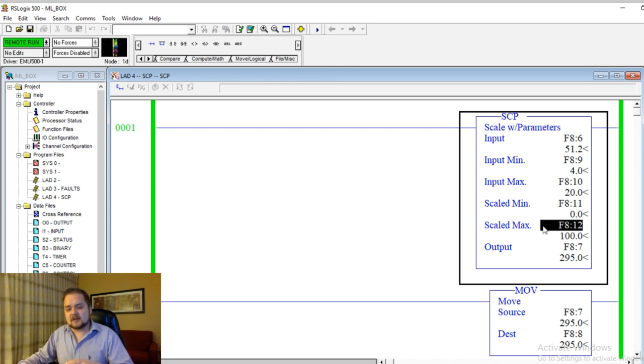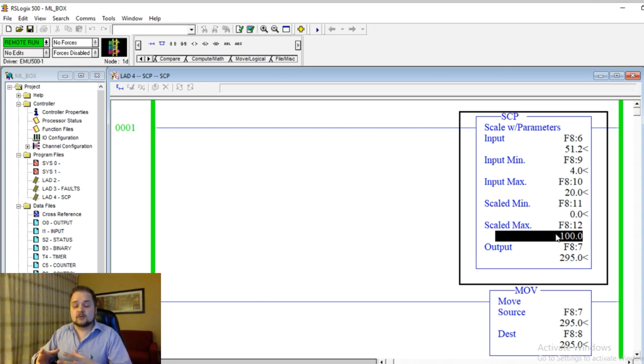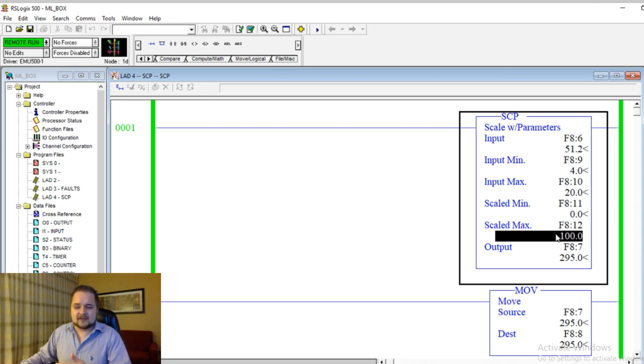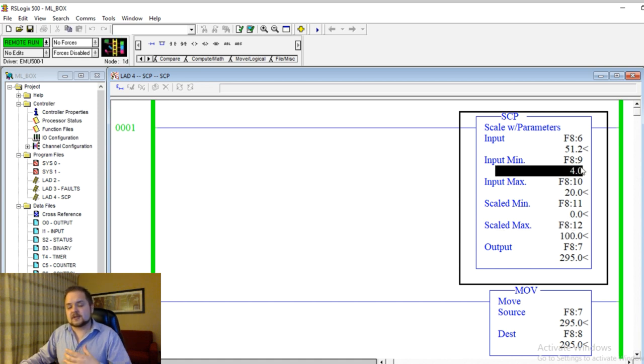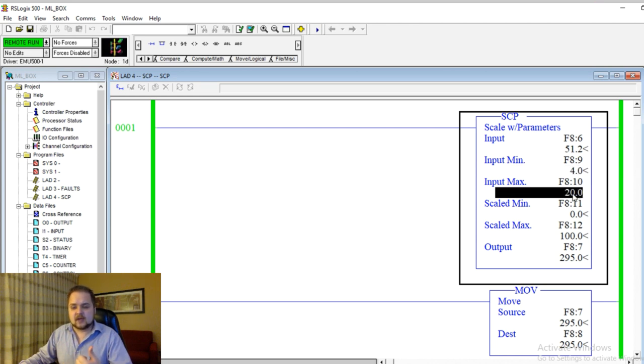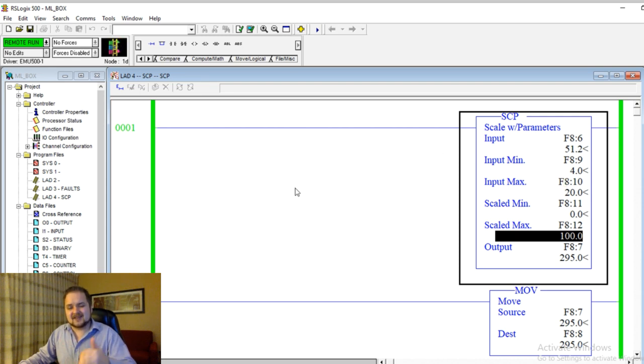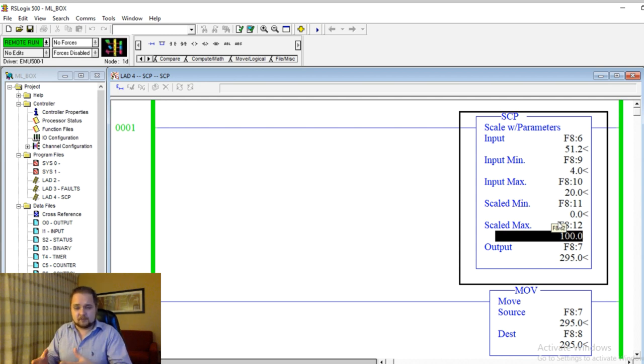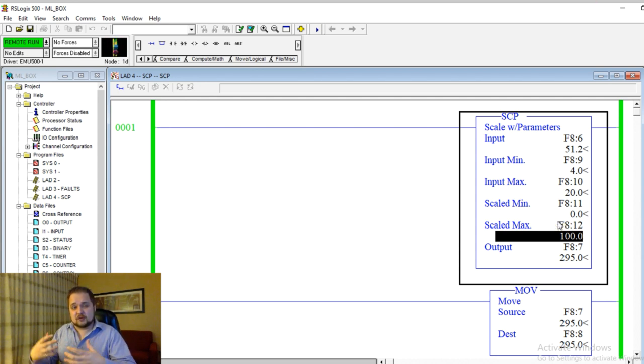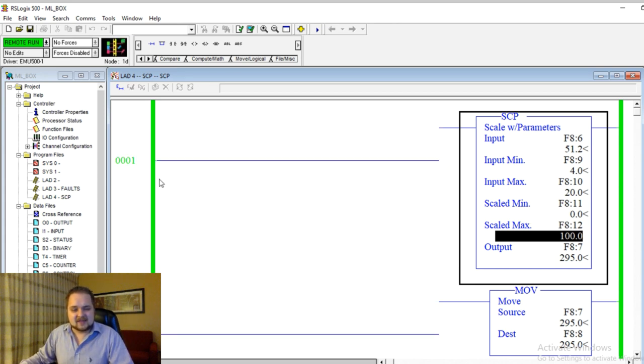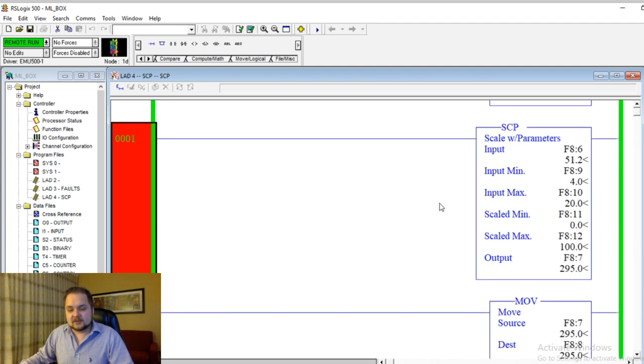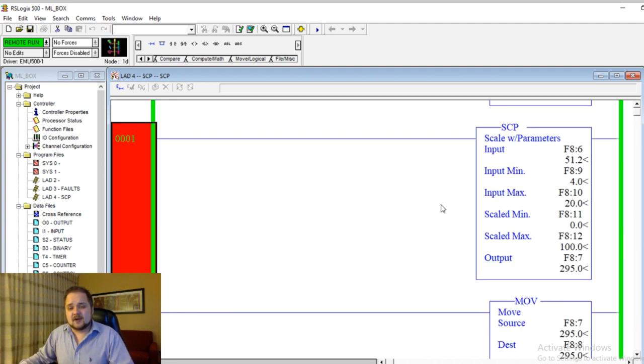Now this might be also chained. So what I mean by that is that zero to 100 on your scaling factor, you can, for example, on your sensors you can read at zero. So when it's sending a 4 signal, it's actually sending you, I don't know, 10 pounds per hour, and at 20 it's sending you 10,000. So now you have this zero to 100 which might be important, but then you can also scale a second time, which instead of scaling from zero to 100 which is going to be a percentage value, you can scale to those pounds per hour so that you can get that information as well. So hopefully that makes it clear on the scaling, very simple instruction, yet very often used in analog situations and sometimes misunderstood.